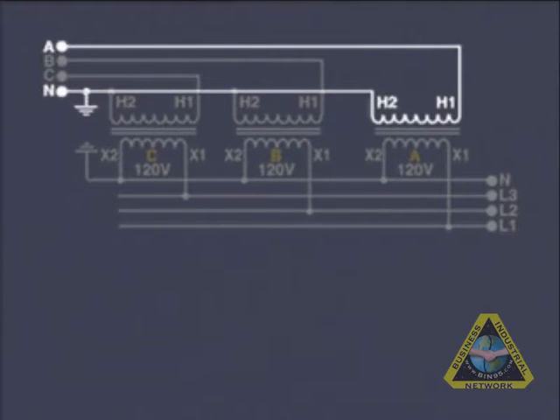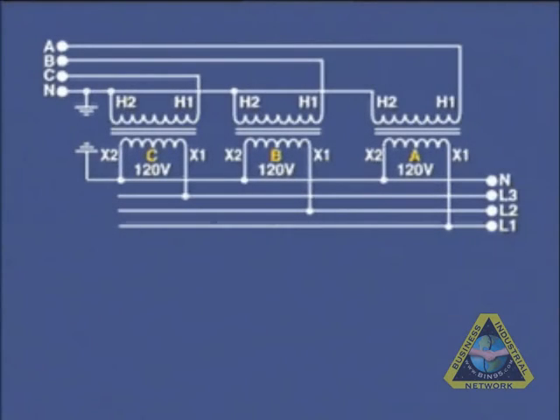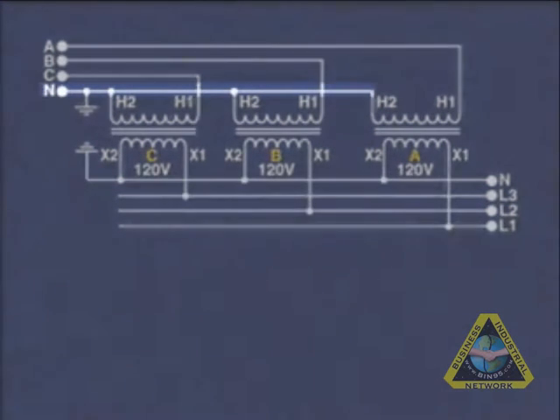From line B, we go to H1 of the second coil, through it to its H2, which also goes to neutral. Similarly, the C phase goes to H1 through the transformer coil H2 to neutral. As we can see, this representation is a Y connection with a neutral wire.